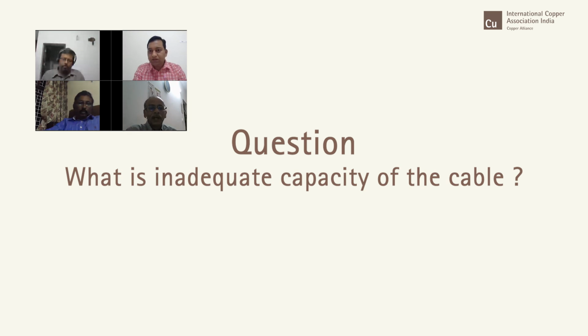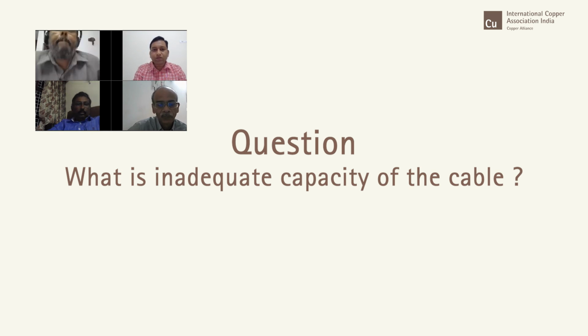So, because the cable has its inherent resistance, if we pass any current beyond that, obviously the cable is going to get heated up. So it is very important to refer to the manufacturer's specification, and he would definitely give the voltage and also the current levels up to which you can use.